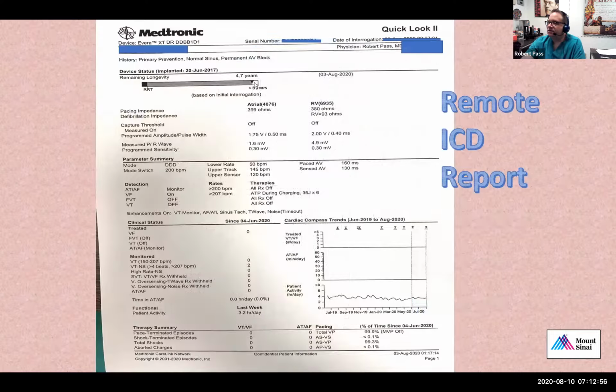Okay. So the next page is where we get all of the information about the device. First off, as Grace said, we're interested in the battery. We see here that we are told the remaining longevity. In this particular case, the device is estimating about 5 more years of longevity. And with this device, I implanted in 2017. So in theory, if this is correct, the device will last approximately 8 years, which is, I would say, about average these days for a defibrillator, especially one that's pacing essentially 100% of the time.